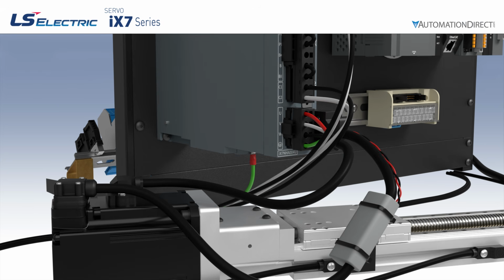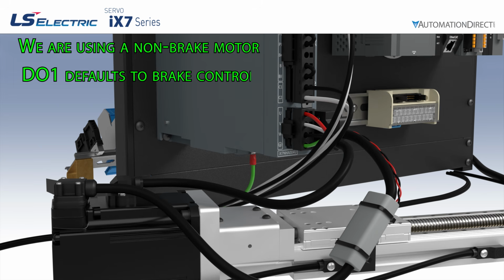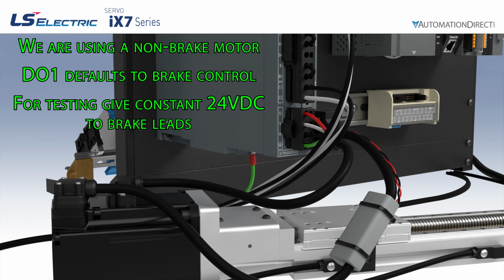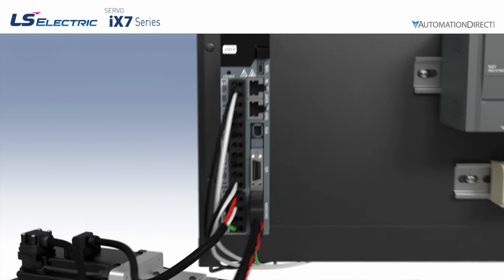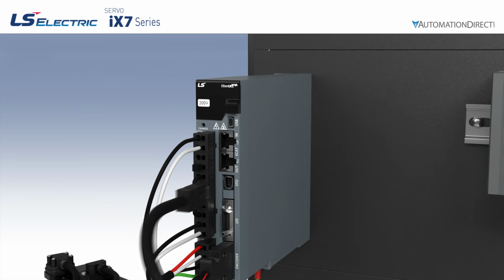If your motor has a brake, wire it to either your external brake control method or to the drive's digital output assigned for braking. This is set to DO1 by default. We strongly recommend you wire a constant 24-volt DC to the brake during initial startup and testing to avoid any mistakes or damage. For STO wiring, use the CN6 terminal.